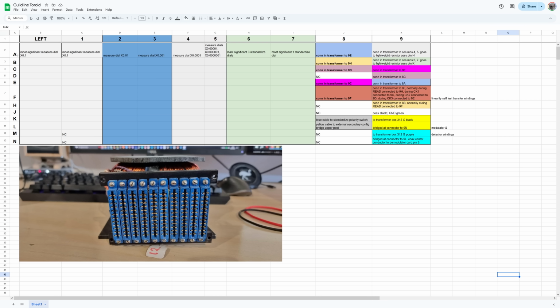It does not have over 2 million windings. Instead, on the least significant windings, which are only worth 100,000th of full scale or less, so any errors get attenuated by that factor, they simply use resistive dividers to feed the dials, and then they are connected in parallel to just one physical actual decade of windings. It's virtual partial windings that behave exactly like the real thing.